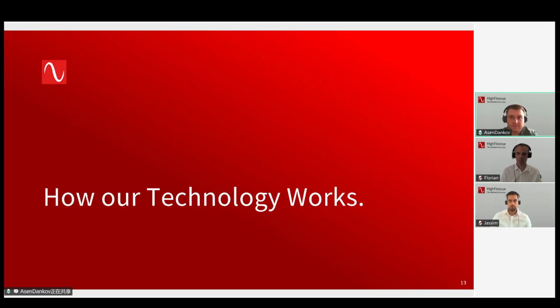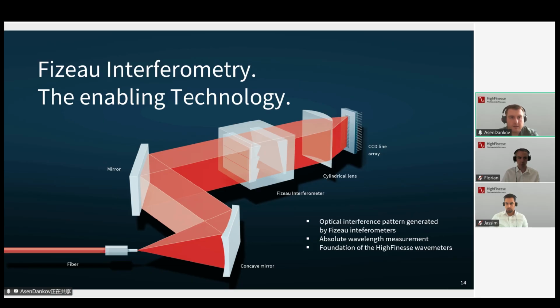Thank you, Florian. Before looking at our products, it is helpful to understand how they actually work. Our wavelength meters are based on the Fizeau interferometer principle. At the core of the success of our wavelength meter lies the Fizeau interferometry. When light enters the wavelength meter through a fiber, it is guided by several mirrors and passes through our proprietary Fizeau interferometer system. Thus, an optical interference pattern is generated and is focused by a cylindrical lens onto the instrument detector. Complex software algorithms then evaluate the pattern and determine the absolute wavelength of the laser.